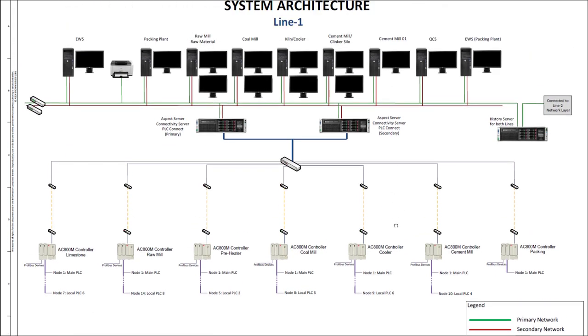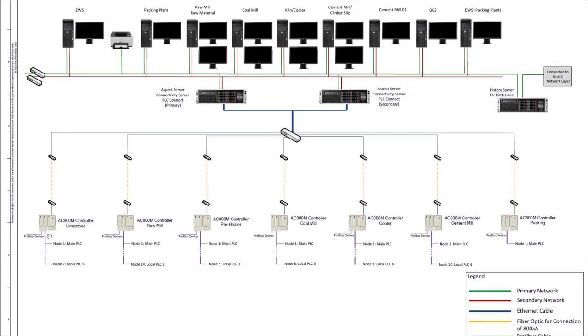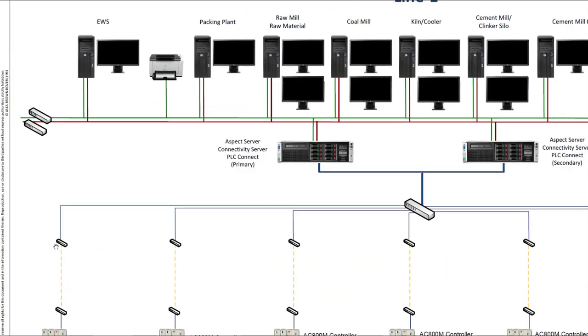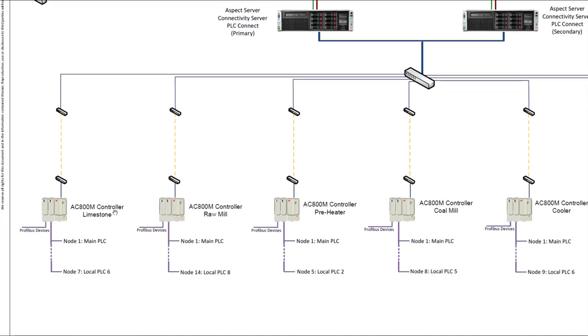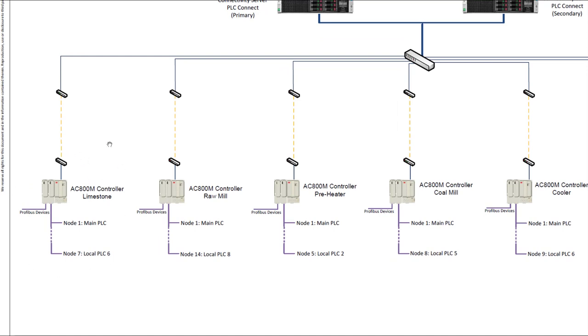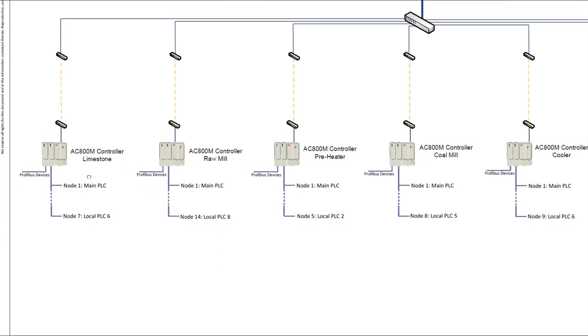I will briefly explain the components in this DCS system. Looking at the PLCs, we have a layer of PLCs. The PLCs used in this case are ABB AC 800M controllers. In a plant — a process manufacturing or discrete manufacturing facility — it is divided into different areas, and each area has its dedicated PLC controller. The valves, actuators, sensors, machines, and induction motors operated in a specific area, such as the limestone crusher, are interfaced with their relevant PLC.